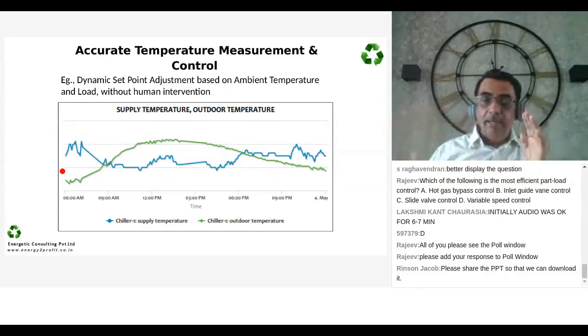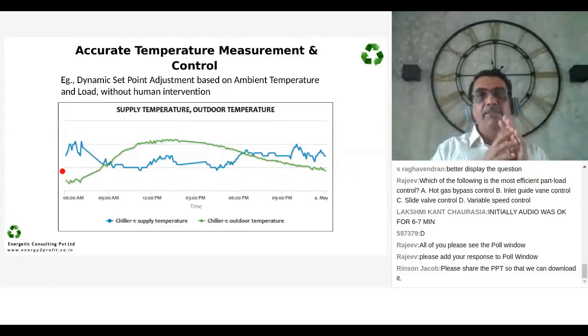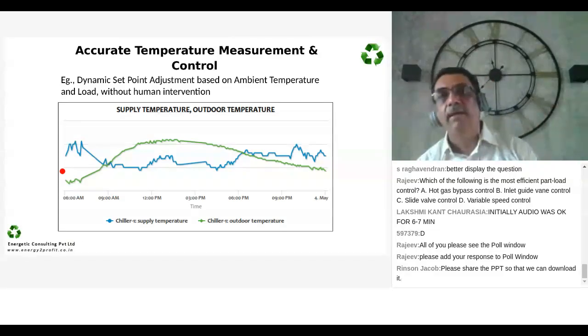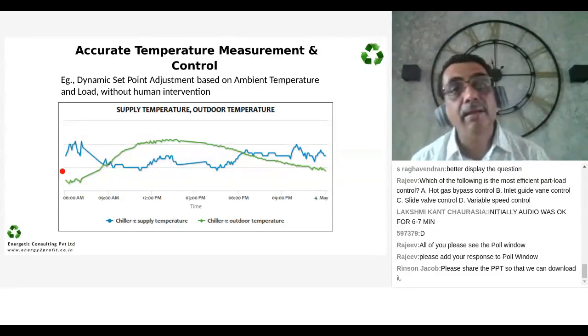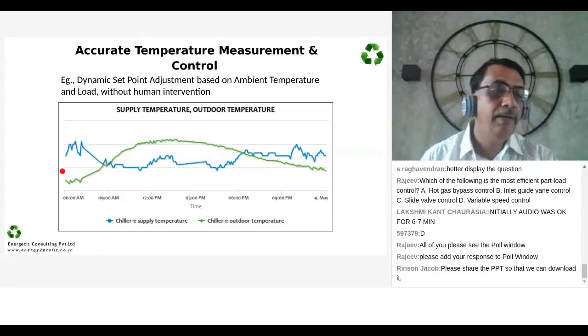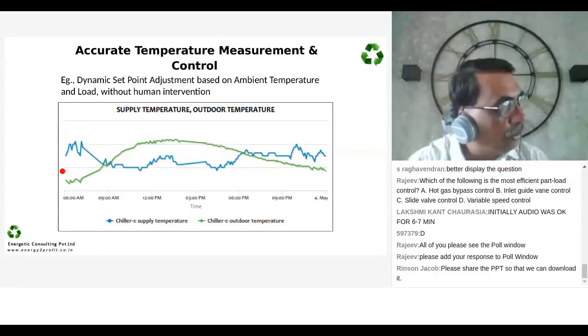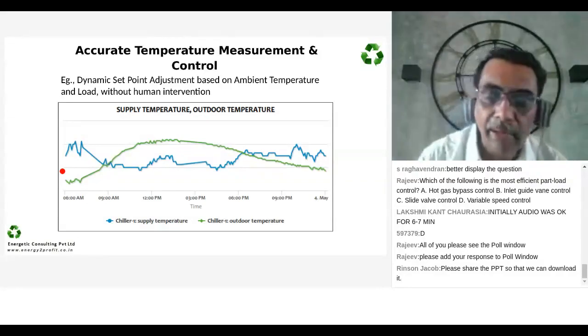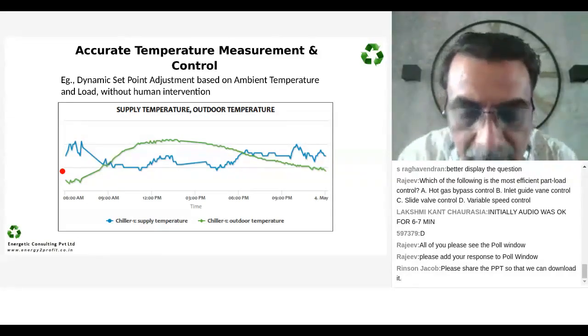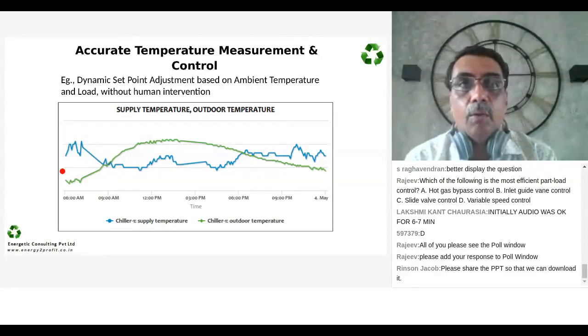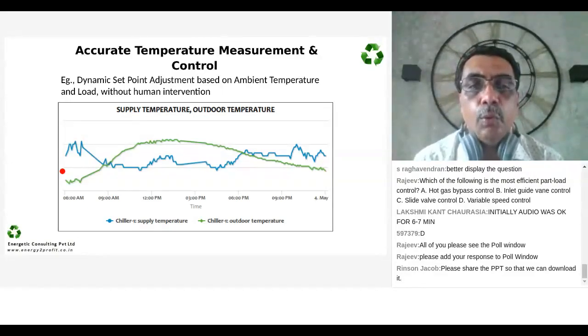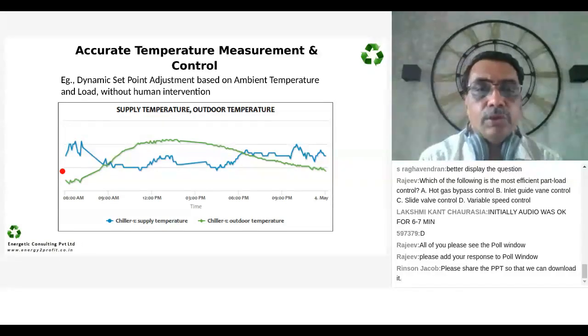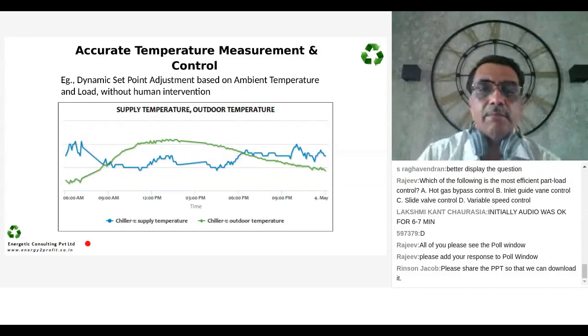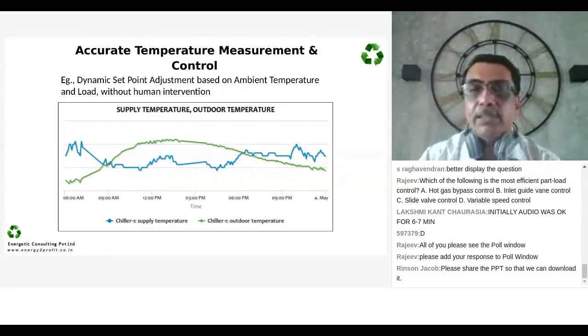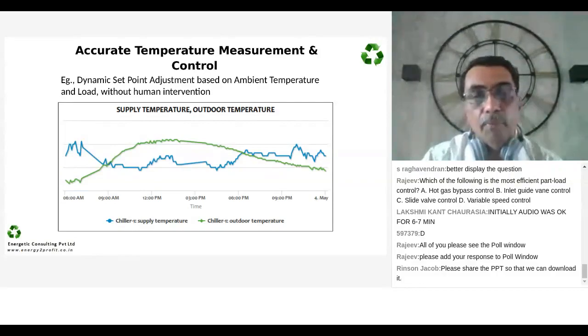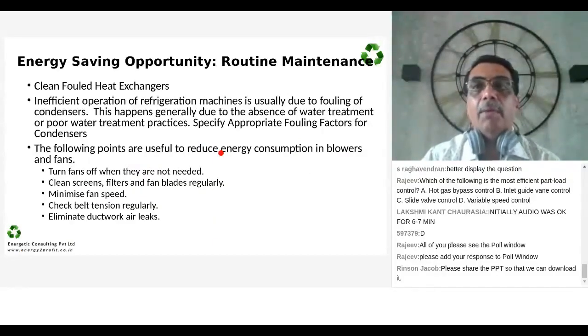So your return air temperature has reduced. So there is a device which takes a dynamic set point adjustment based on the ambient temperature and the heat load, which is measured in the return air temperature, which means when there is no load, it raises the temperature of the air which is given to the space by using a dynamic control. Now this is missing, and this is huge potential to save. Something like 8 to 20% savings are possible with this kind of a floating control. Very significant. And there are controllers available.